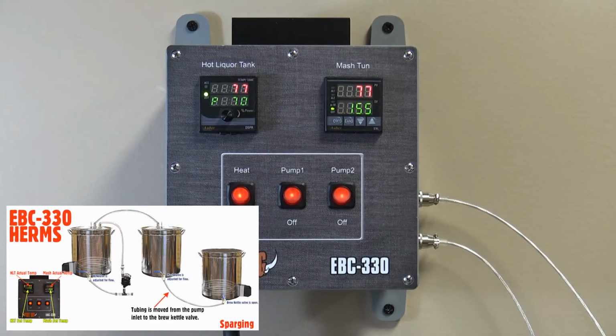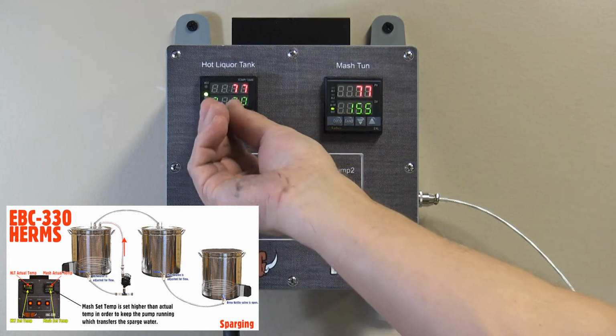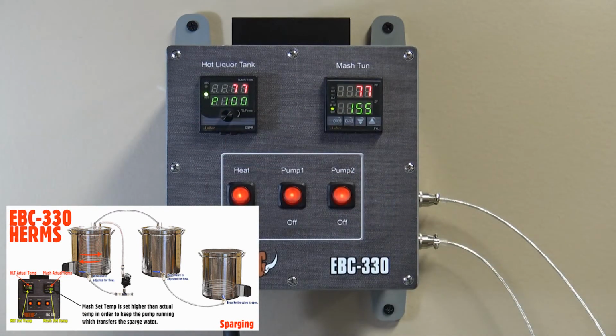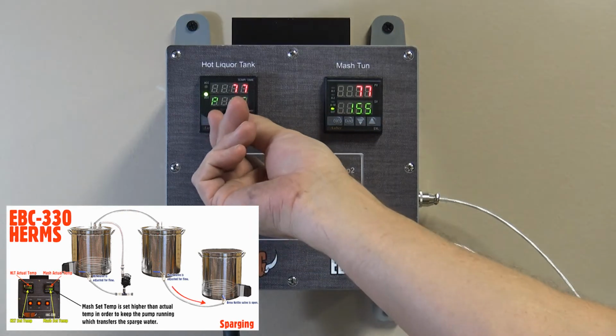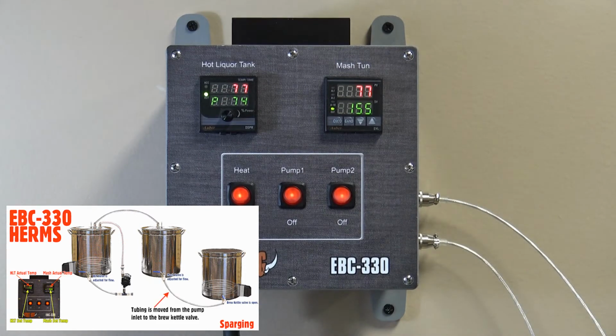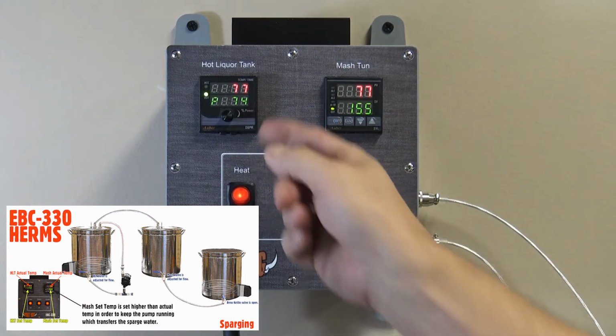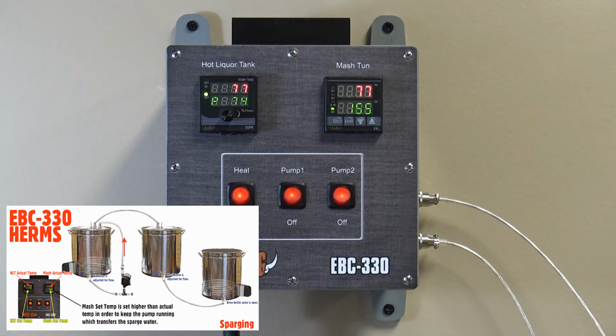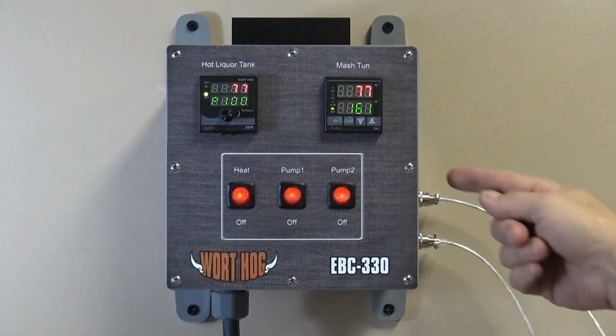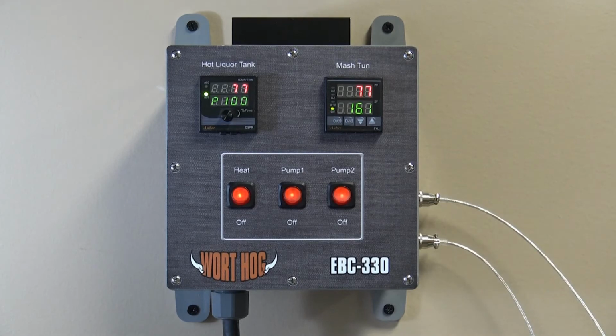In this mode, you're selecting a percentage of power from 0 to 100%, and you would simply run it up to 100% until you reach a boil, and then dial it back as it gets close to something perhaps around 70%. Note that in the boil mode, the change is immediate. It's not necessary to bump the knob to save the change. It's immediate, like so. This controller is fully overload protected. It's got a 30 amp main breaker on this side and a 10 amp breaker for the 120 volt subsystem.